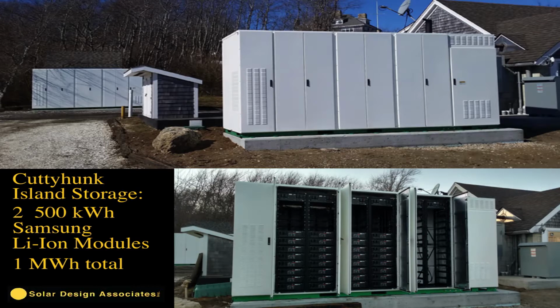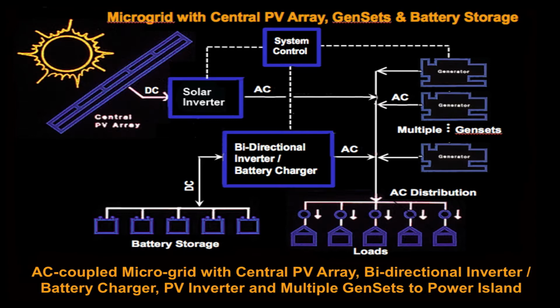The system: solar feeds AC to the grid. The existing generators the island was running on were retained for backup, since they're paid for and in place and functioning. There's a very large battery bank with a bidirectional battery inverter charger that can charge from the generators or from the solar on the AC side, then distribution across the island.